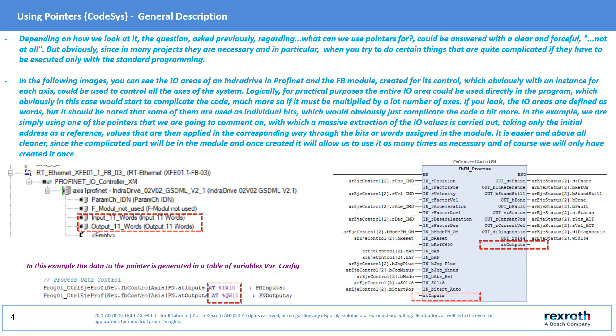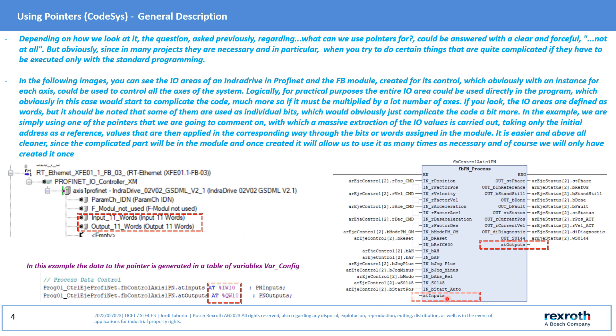The previous question can we answer it with the attached example. In the example that appears in the image, the I/O areas of an IndraDrive in PROFINET are being accessed with 11 input words and 11 output words, which are read and written with a pointer inside the FB that has been generated for access control.